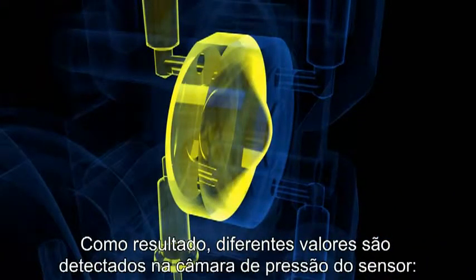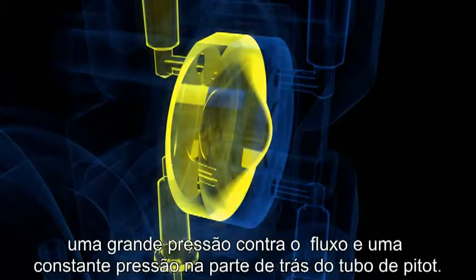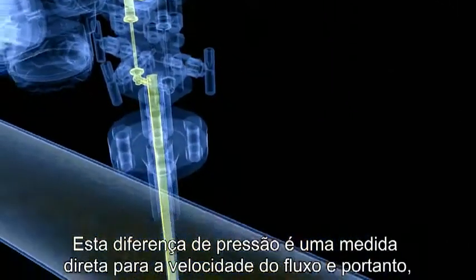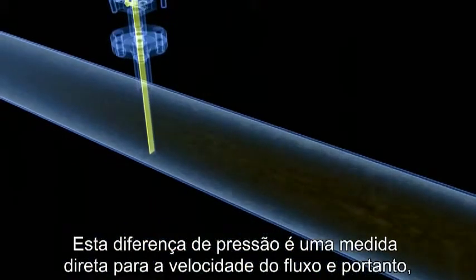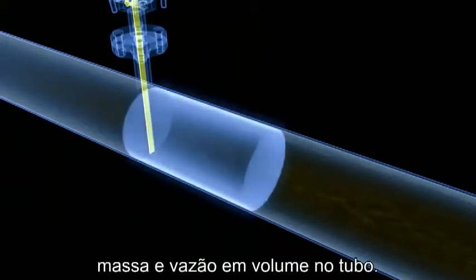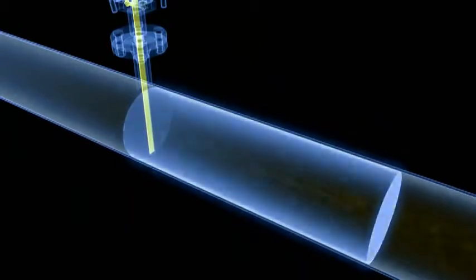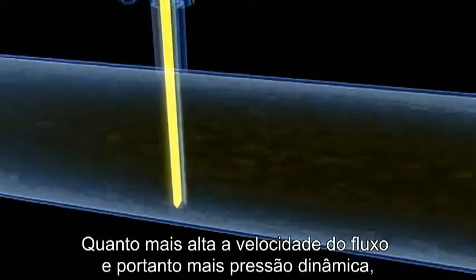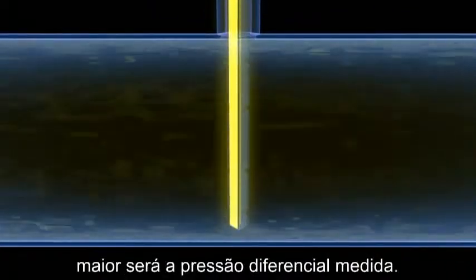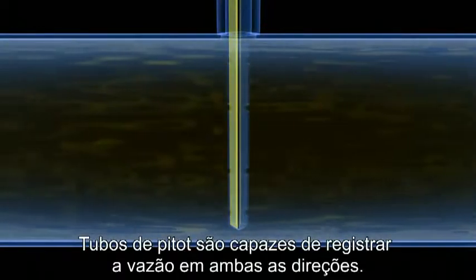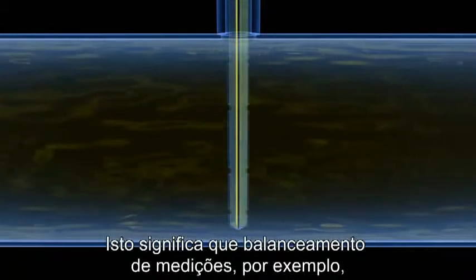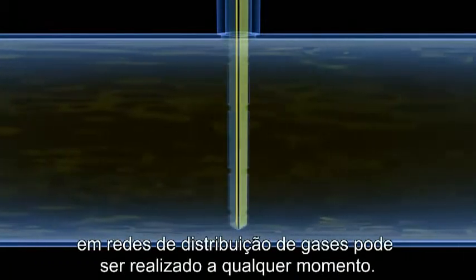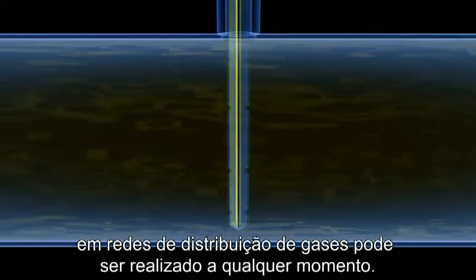As a result, different values are detected in the pressure chambers of the sensor. Higher pressure against the flow and constant pressure on the rear of the pitot tube. This pressure difference is a direct measure for the flow velocity and thus the mass and volume flow in the pipe. The higher the flow velocity, and therefore the dynamic pressure, the greater the differential pressure measured. Pitot tubes are able to register the flow in both flow directions. This means that balancing measurements, for example in gas pipeline networks, can be carried out at any time.